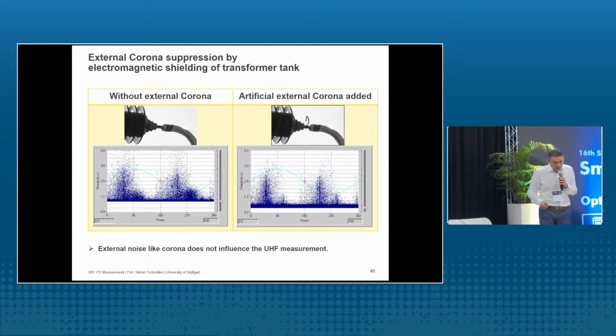The first example shows the influence of external corona. So we had here a transformer and an offline measurement, so not the grid voltage, an offline measurement. The advantage of the offline measurement is that the noise is a little bit lower. And we measured here the UHF signals inside the transformer tank. Yeah? So this is the so-called PRPD pattern. Then we added a strong external corona by fixing a wire here on the connection. And on this wire, of course, we had very strong corona in air, but the PRPD pattern was exactly the same as before. Yeah? So the external corona didn't influence the internal PDs.